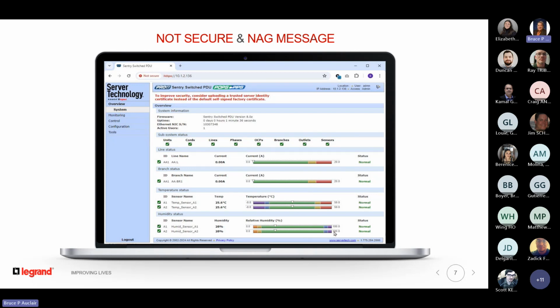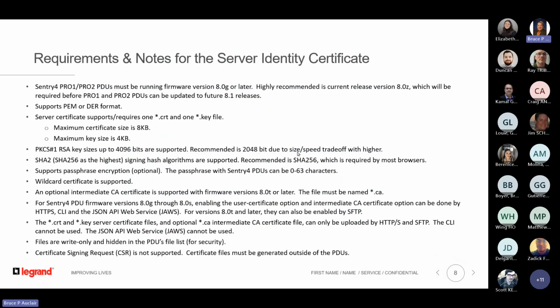Now, these are the requirements and additional information needed to install a proper trusted identity certificate into a Server Technology PRO1 or PRO2 PDU. They must be running firmware version 8.0G or later, because that's the release that introduced TLS 1.2. We highly recommend the current release, version 8.0Z, partly because it will be required for all PRO1 and PRO2 units to be updated to future 8.1 releases.